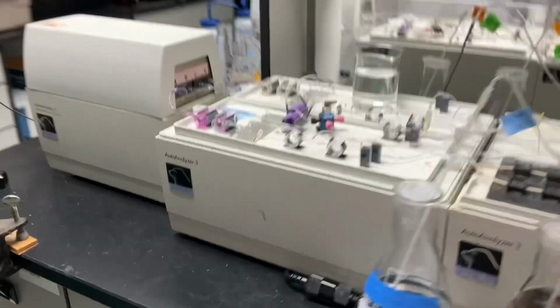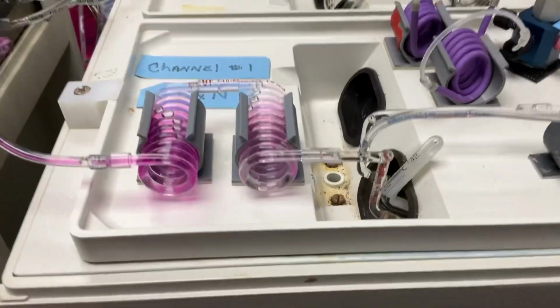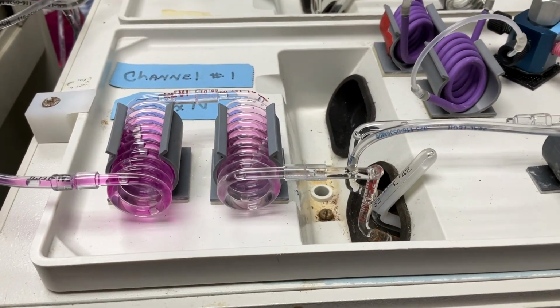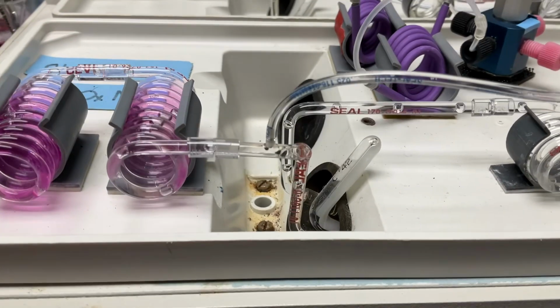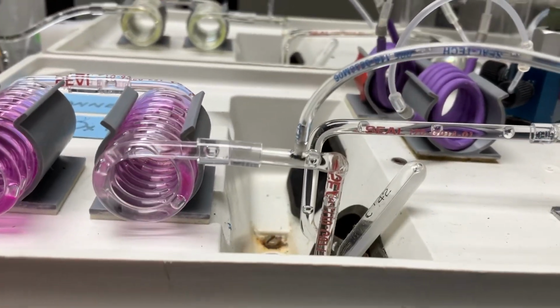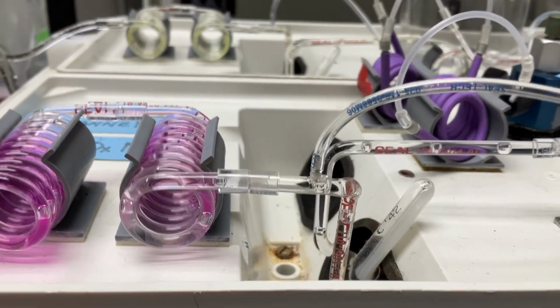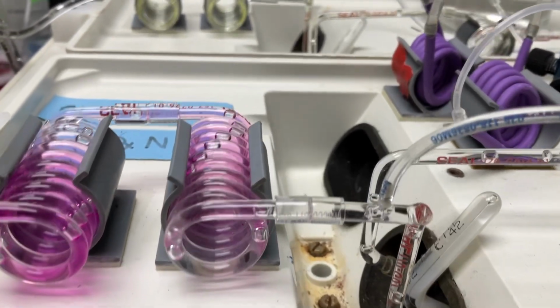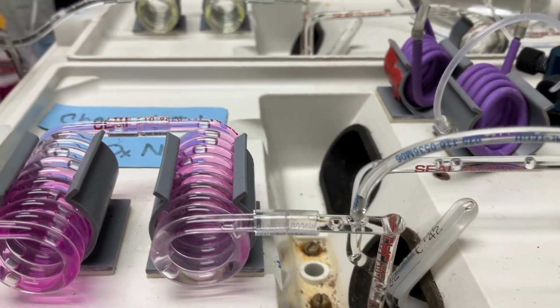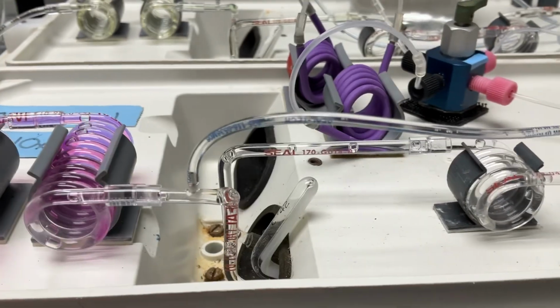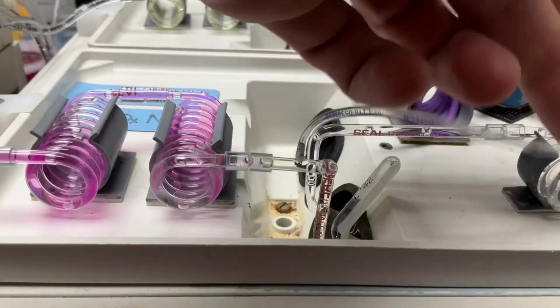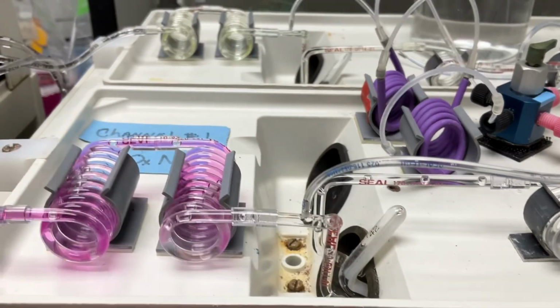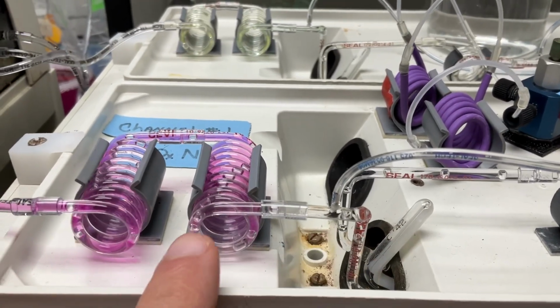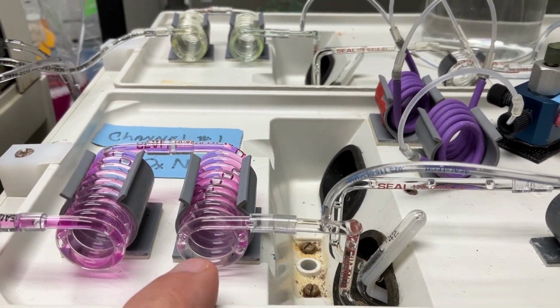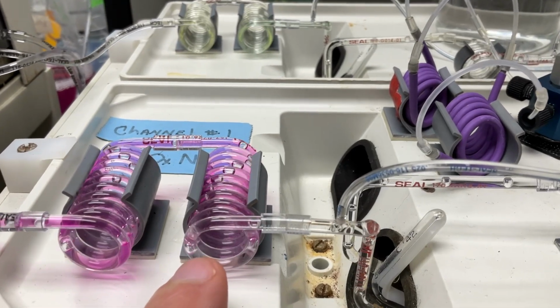So basically the machine, as it goes along and it's processing things, it can kind of lose some of its ability to detect at that high range. So by consistently checking, you can account for any drift as it goes. And you can see that color response there is a little strong, that bright pink color. This particular sample isn't really exerting a color response for ammonium, so it probably doesn't have a lot of that. That line, that tube right there, is actually what's delivering what's known as sulfanilamide, which is the color reagent used in this analysis that actually forms that pink color.